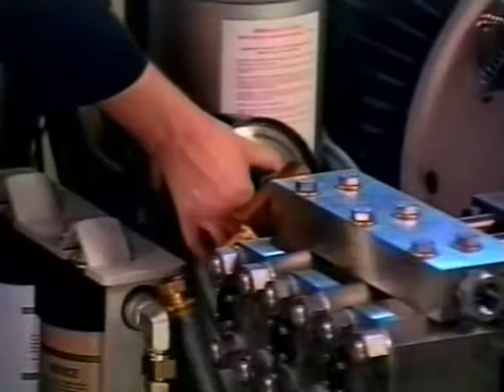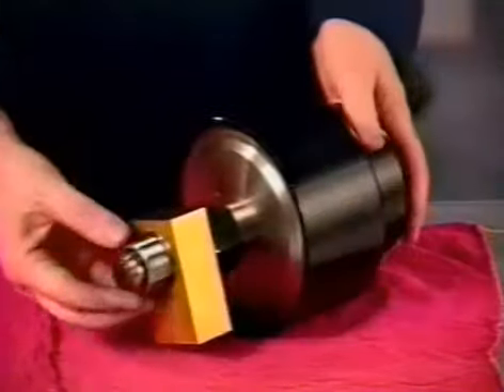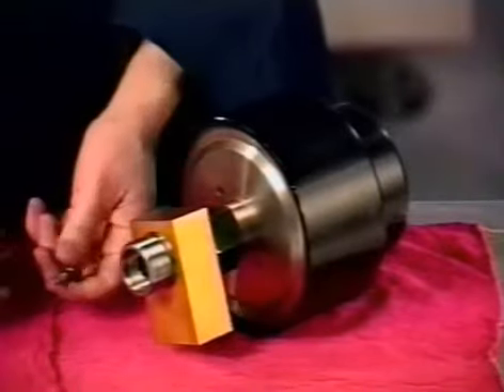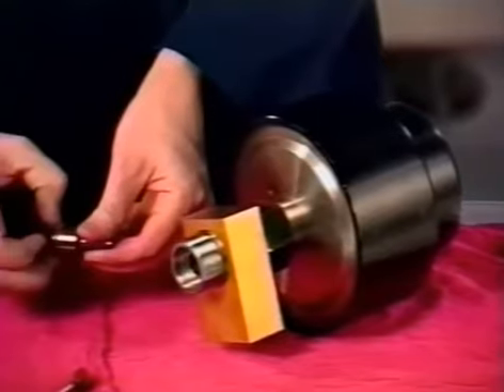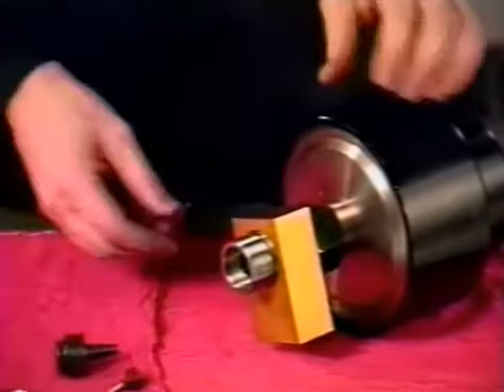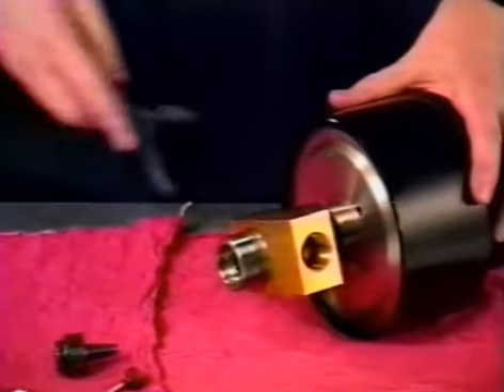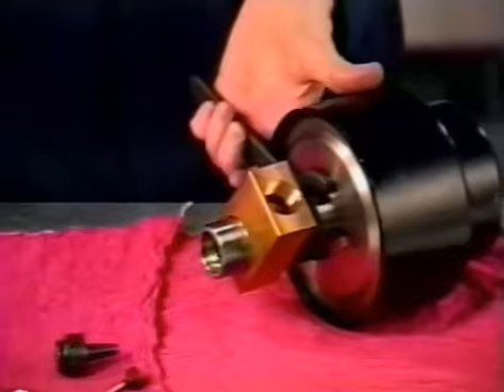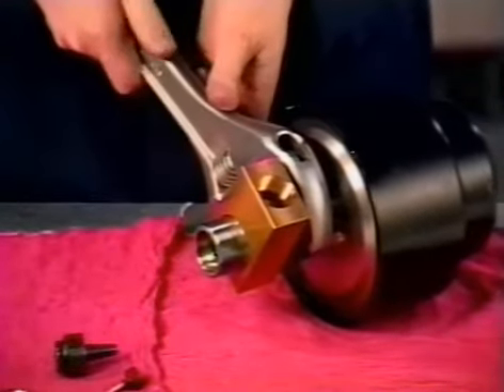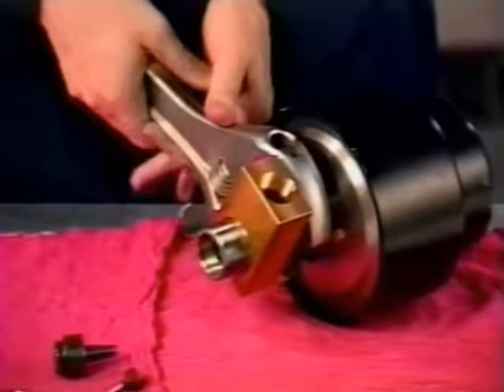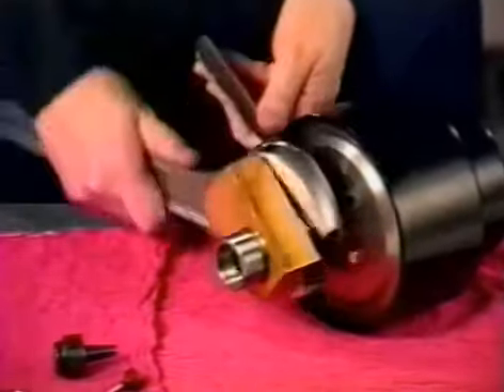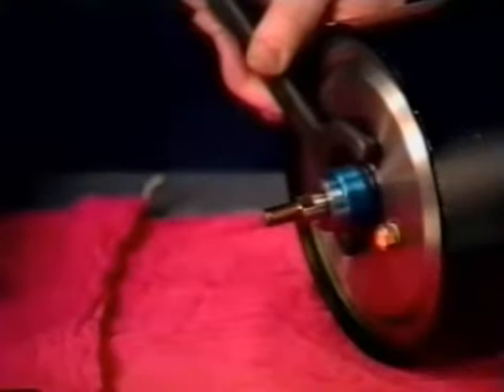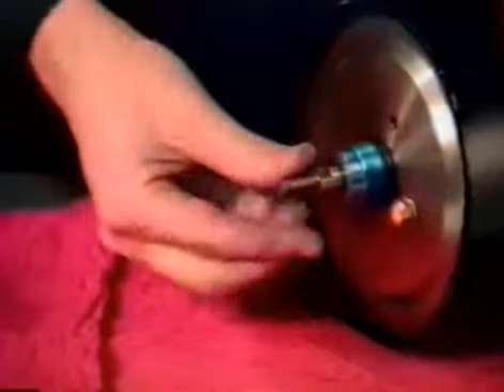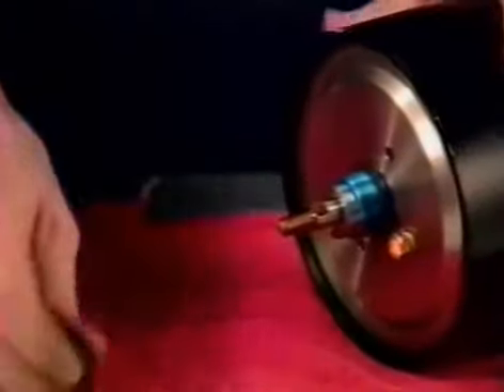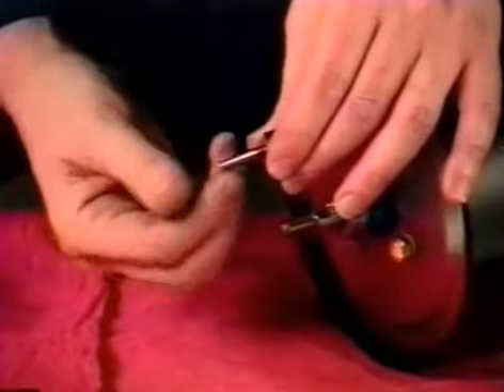Next, unscrew the valve from the high-pressure manifold. Set the valve on a workbench. Remove the poppet and seat. Remove the seal from the poppet seat. Replace the seal only if there is evidence of cracking or erosion. Now remove the body from the actuator. Inspect the plunger assembly. If there are erosion marks on the plunger assembly, replace it.